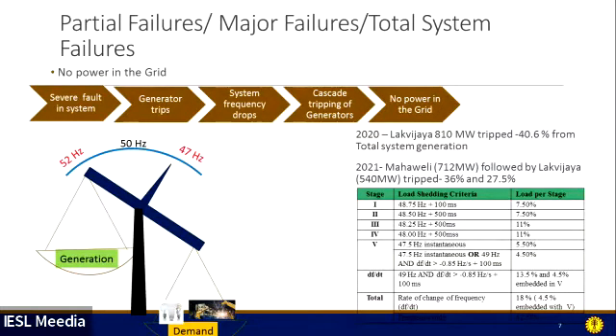In 2021, there was a fault in the transmission network, and consequently generators tripped: 712 megawatt from the Mahaweli, and after some seconds, Lakvijaya tripped, rejecting 540. So altogether, around 50 to 60% generation loss, and we cannot recover the system. Because our system is very small, our system inertia is small. I mean, our system does not have much strength. We cannot say exactly weak, but it's not very strong. So we cannot sustain that much generation loss.